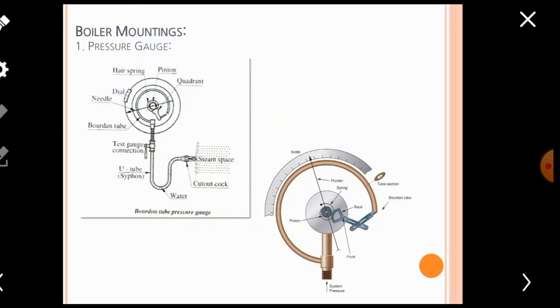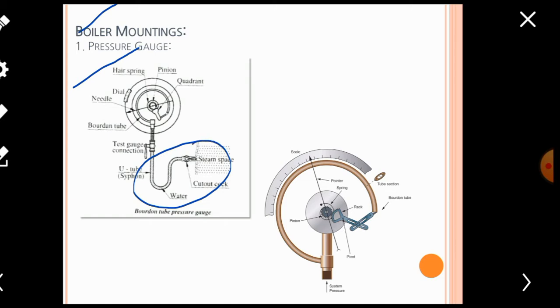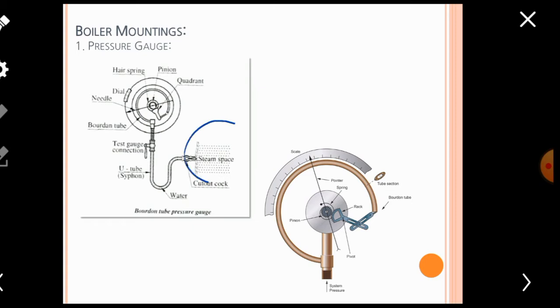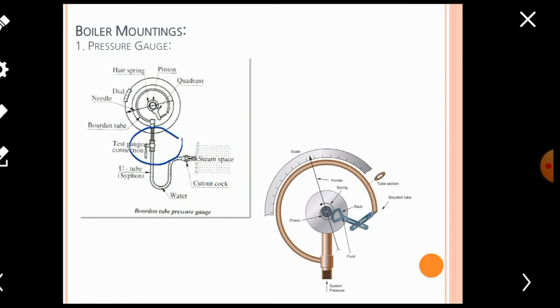Now we are going to discuss in detail the various types of boiler mountings. The first type is the pressure gauge. The basic function of the pressure gauge is to measure the steam pressure produced inside the boiler. Looking at the constructional detail: at the bottom there is a U-shaped siphon tube, one end of which is directly connected with the steam space of the boiler drum, whereas the other end is connected with a pipe provided for the test gauge connection. There is also a Bourdon tube — one end connected with the test gauge connection, the other end connected with a specially designed gear rack or quadrant.